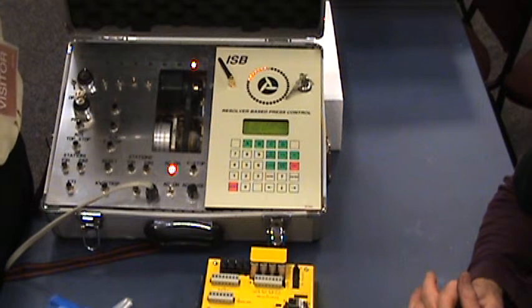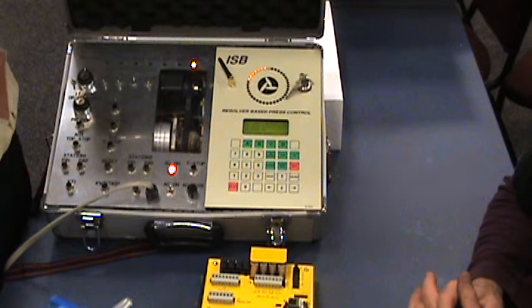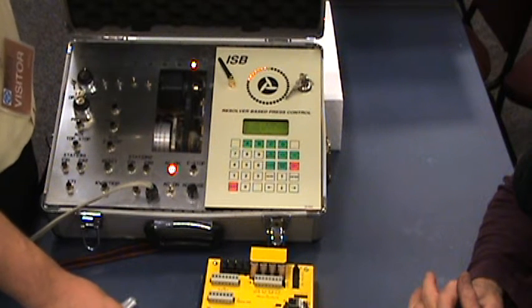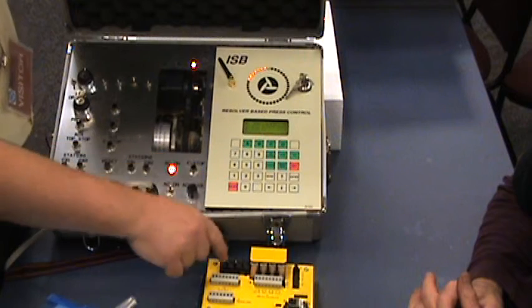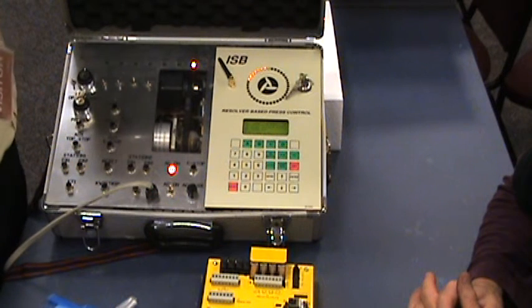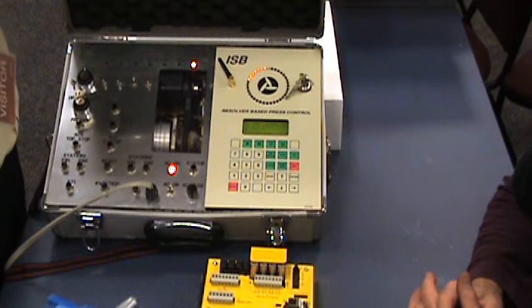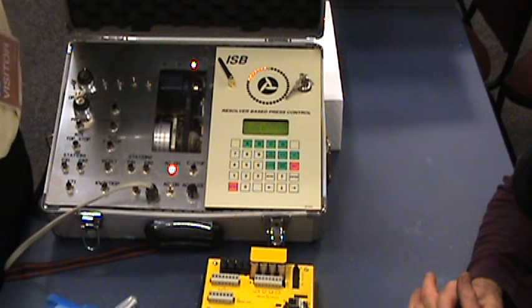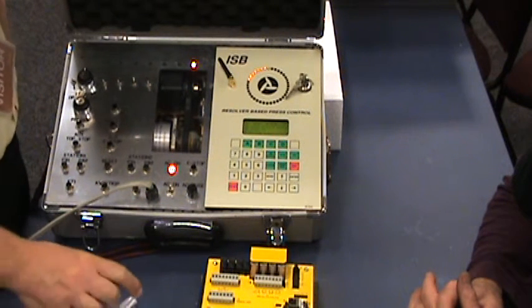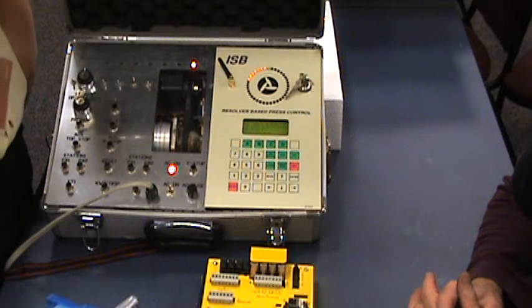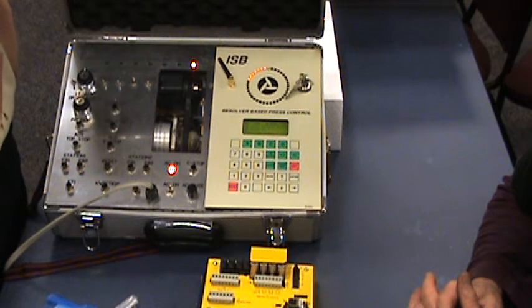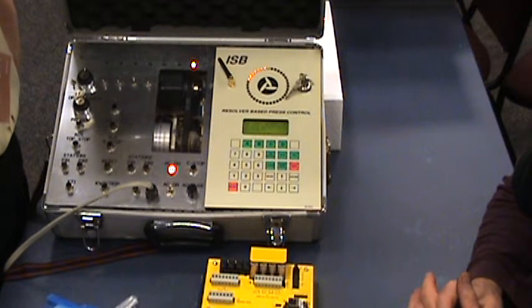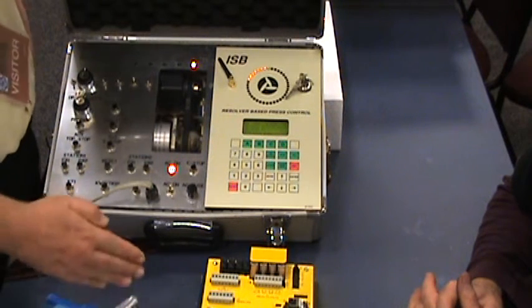So, if you're running applications where you're turning on and off solenoids or any high current device, you could use either the AC or the DC solid state relay that we supply spares. You can unplug these and plug these into the same socket. So now the mechanical relays have been replaced with solid state relays. Solid state relays will last for many years of trouble free operation. The reason why we don't put them in standard unless you ask for them is because they're solid state, you have to know what you're controlling with them.